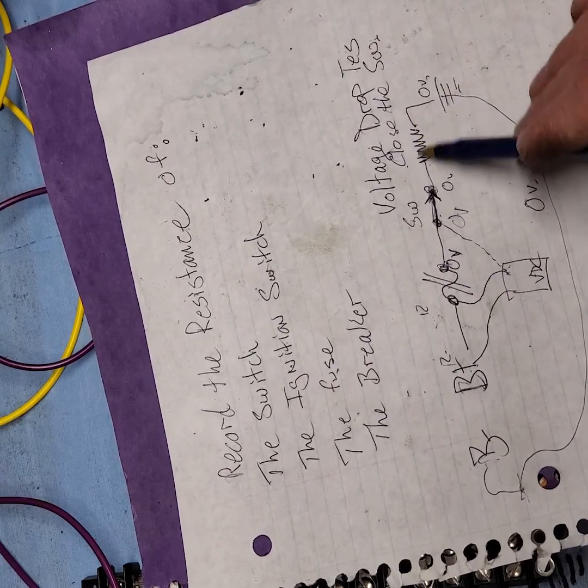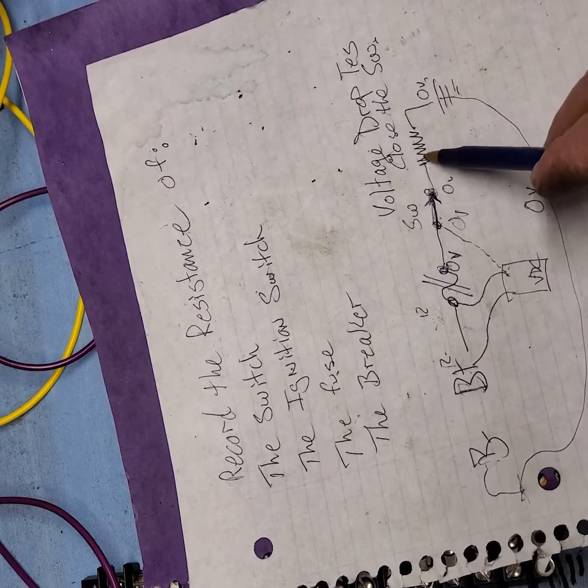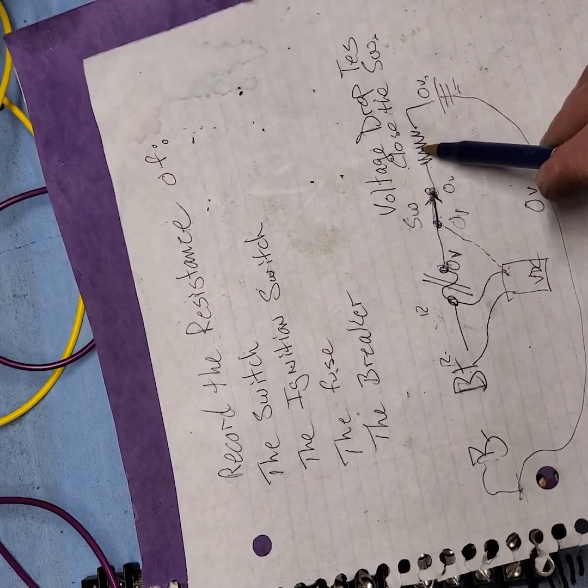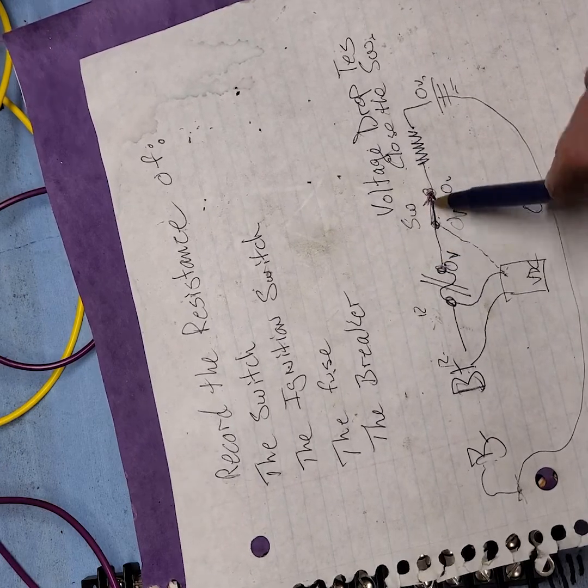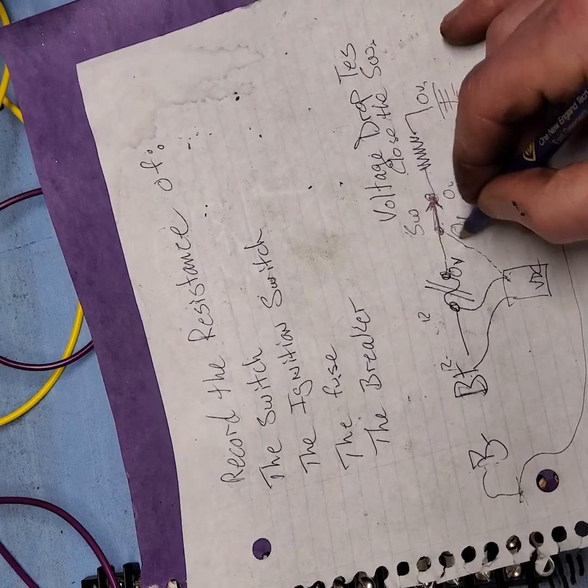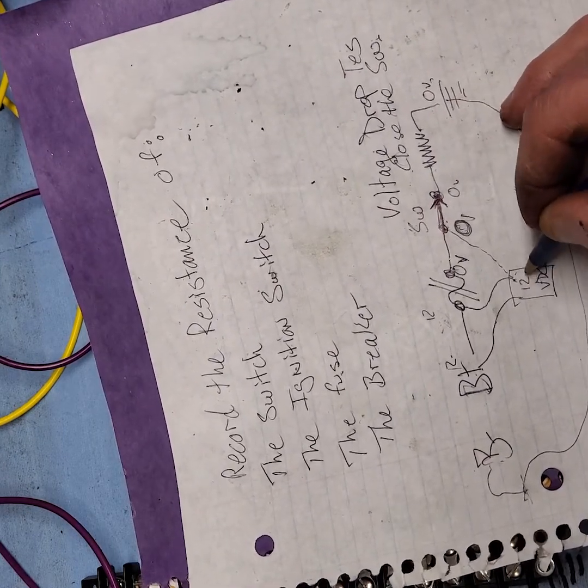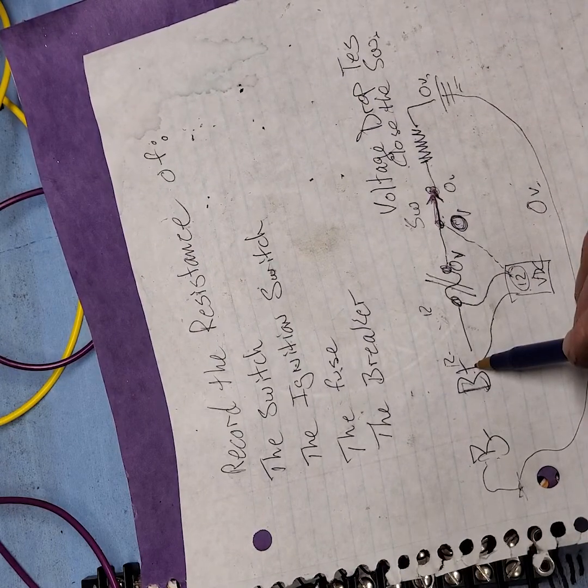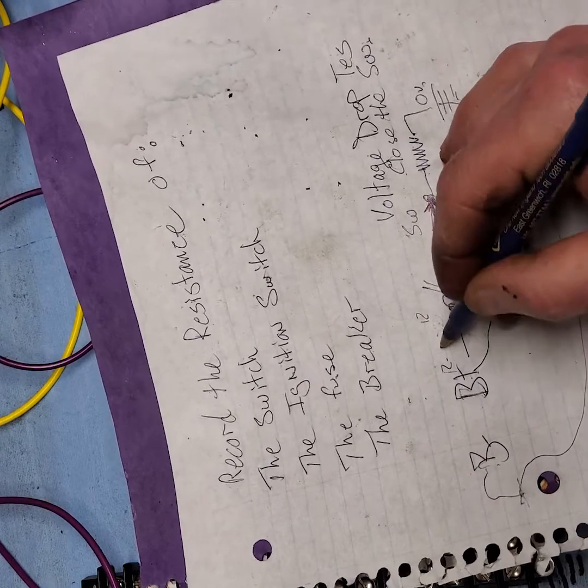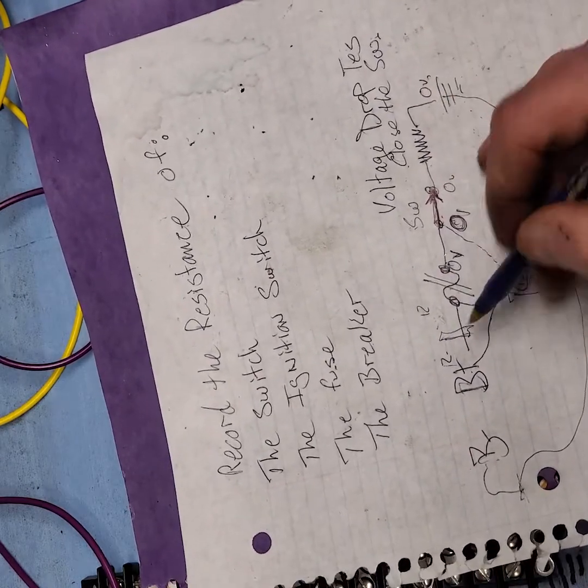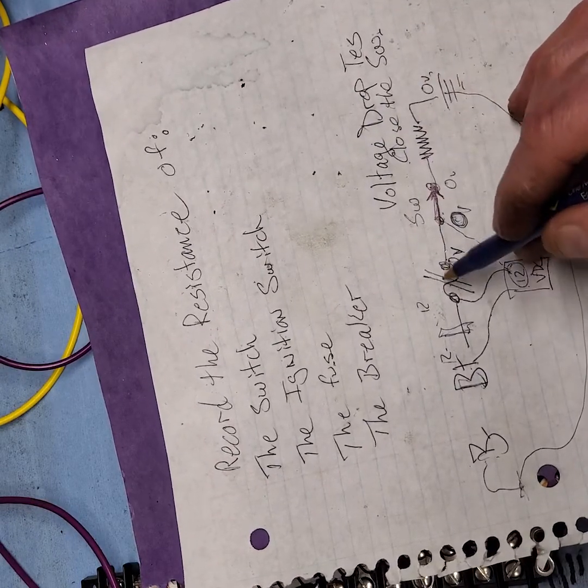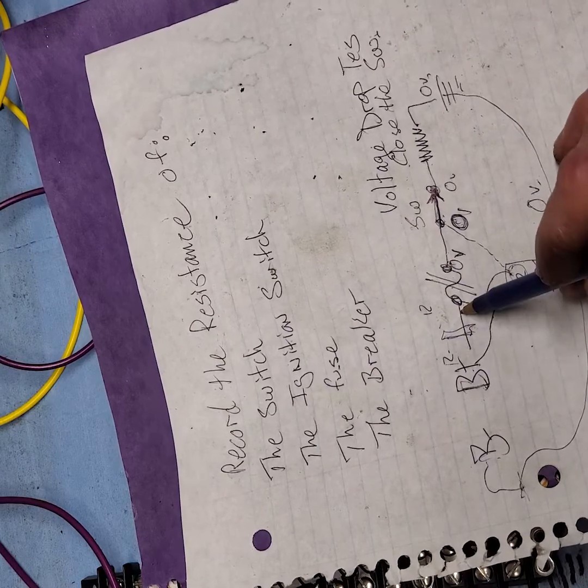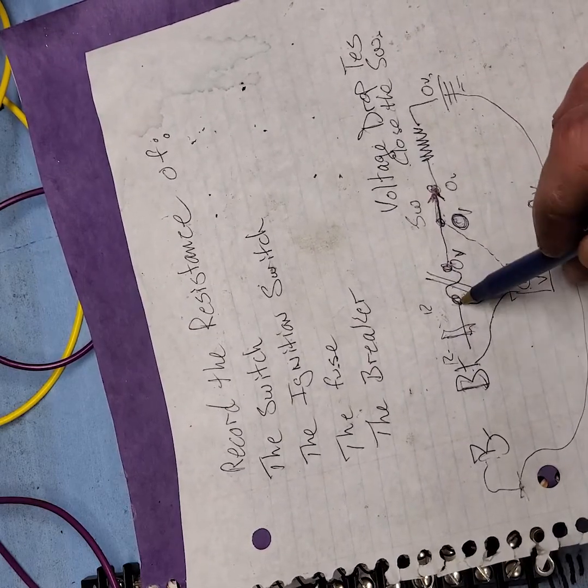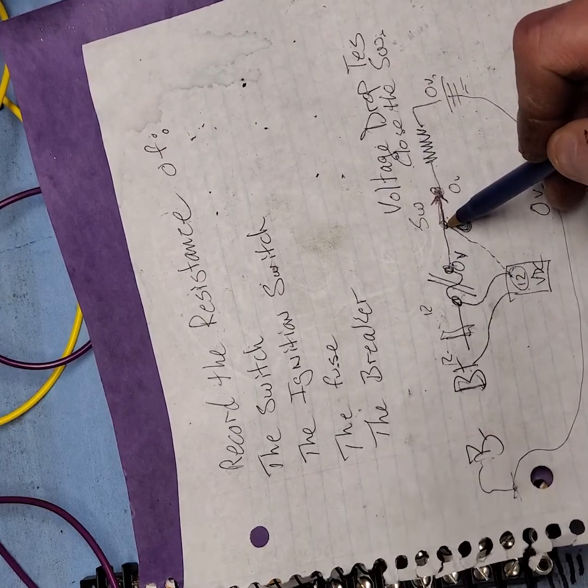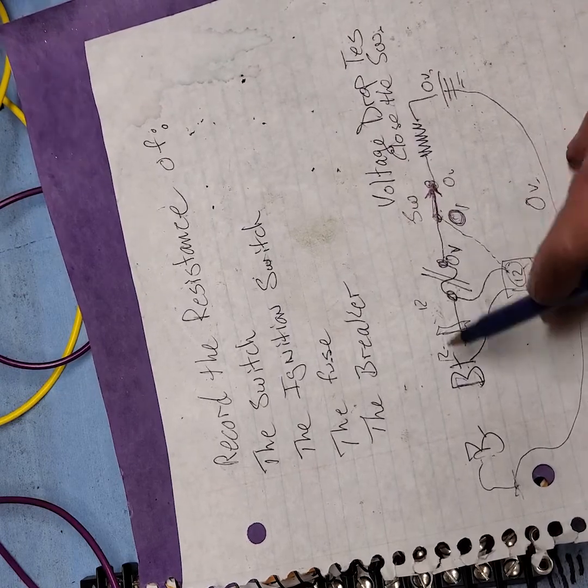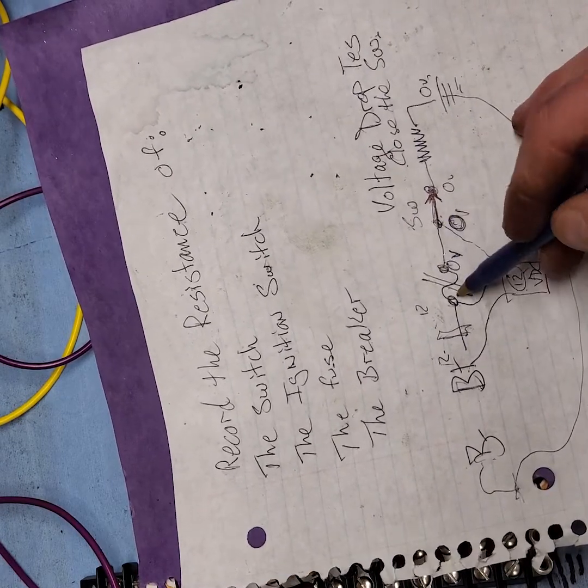The load device, remember, has continuity. The coil of wire inside that pull-in coil has continuity. So when I put my meter lead on this side of the circuit, I now have a ground, which is 0 volts. My meter now reads 12 volts because I have a power supply I've tested. So I put my meter lead on this side of my circuit at the battery, or if I could put it on another place, someplace before the battery, before that circuit breaker, I would have voltage potential. And then when I put it on this side, I have no voltage. I have ground. And that tells me that I have an open circuit.